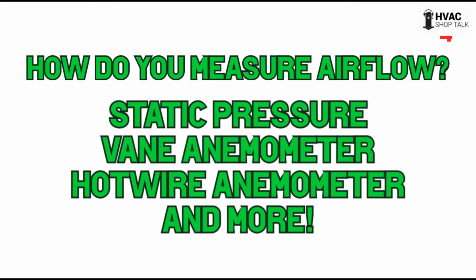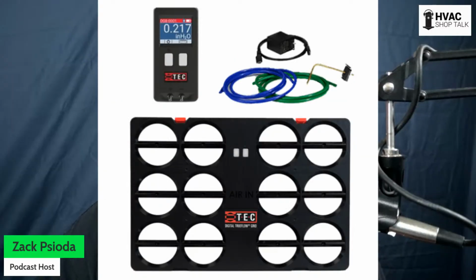In the HVAC trade, I'm talking about normal things. How will normal average humans with their normal average amounts of money be able to measure airflow? We have static pressure, very common. Vane anemometer, which is a word I love to say because I can't wait to say anemometer later in the show. A vane anemometer. We have hot wire anemometer, and there's more. Okay, I'll go ahead and tell you, we're not going to go into the more right now, but I'll show you. This is the True Flow grid.